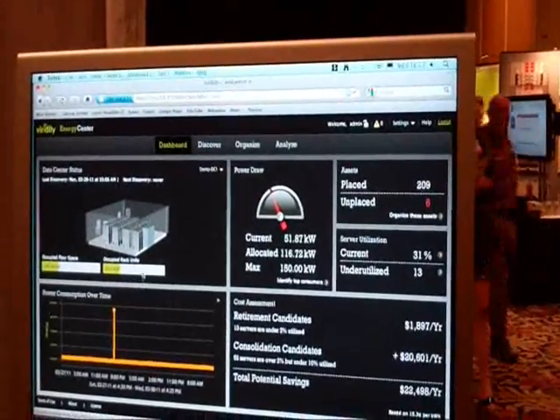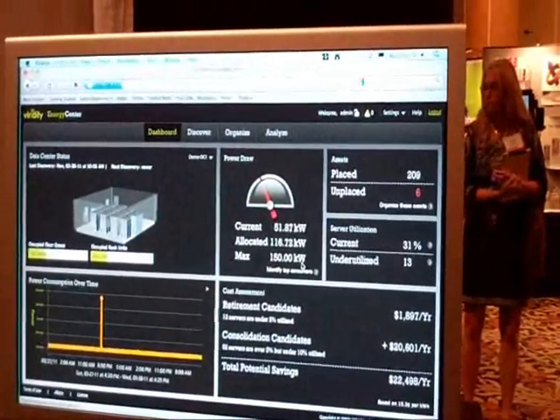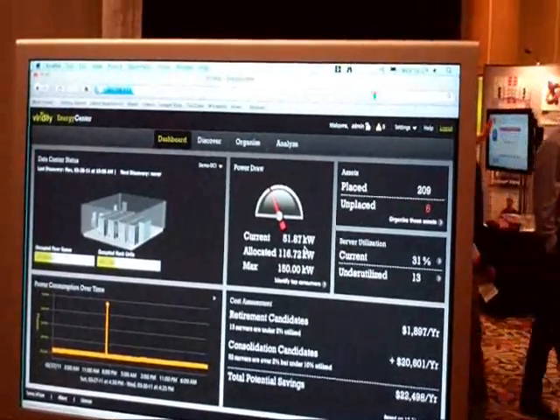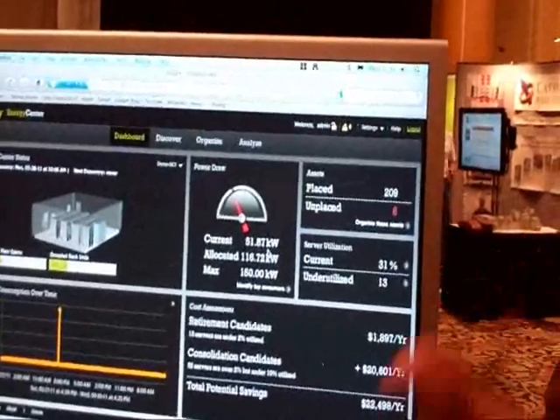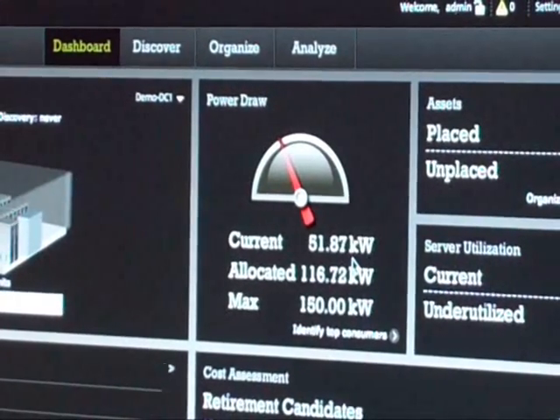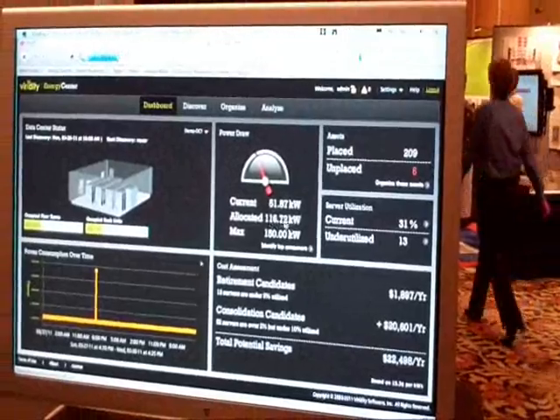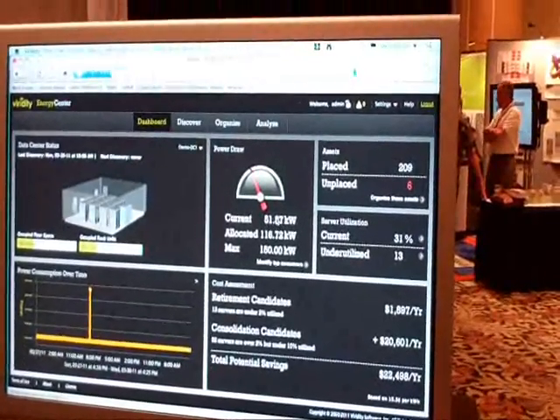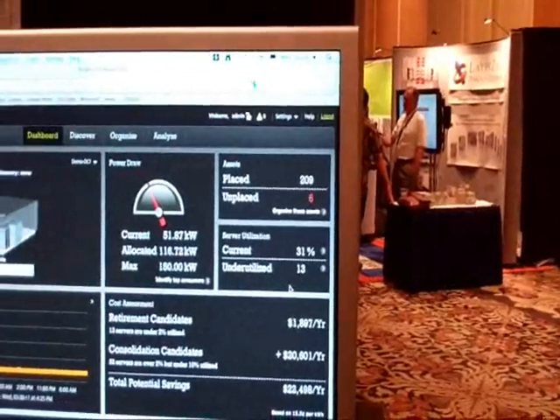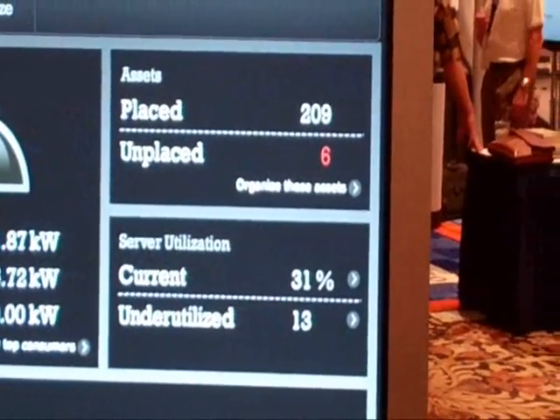In the dashboard you've got basically a picture of what your data center looks like, the current power draw — which gives you how much power you have coming into the facility altogether, how much you've allocated to the servers if everything was running at 100%, and how much power you're actually drawing right now. One of the things that makes capacity planning so difficult is that laptop battery management technology has eked into the server side, so a server these days can actually double or triple its power consumption based on utilization. While if everything was running at max we'd be at 116 kilowatts here, right now we're only running at about 51 kilowatts. It gives you a quick picture of your assets, current utilization rates, and what kind of savings you're looking at.